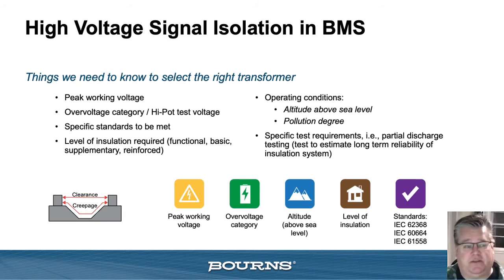One of the first is to establish what your peak working voltage is, or really the highest input voltage that the primary of the transformer will see. If it's high enough, either through a transient state or open or closed circuit operation, it may have to contribute to an overvoltage category, which is part of the standard itself. That would be akin to more stringent testing, or maybe an increase of creepage and clearance distance, which I can move into in the bottom left part of the slide.